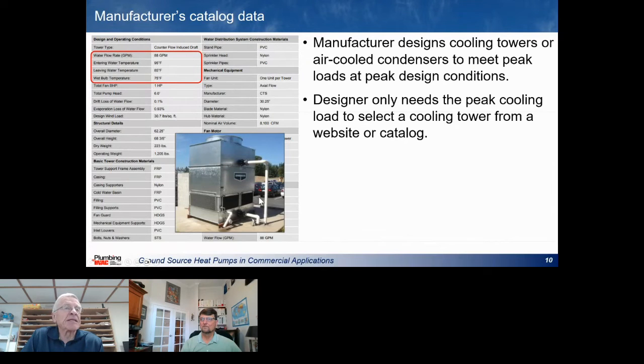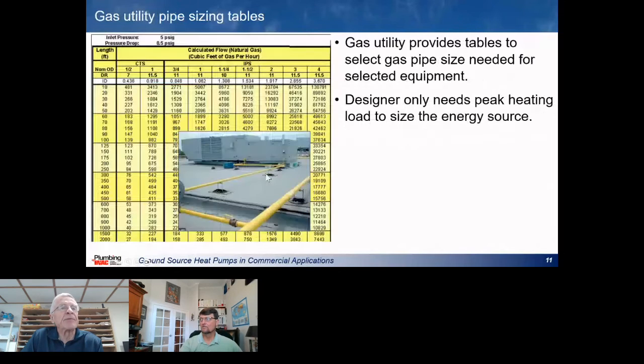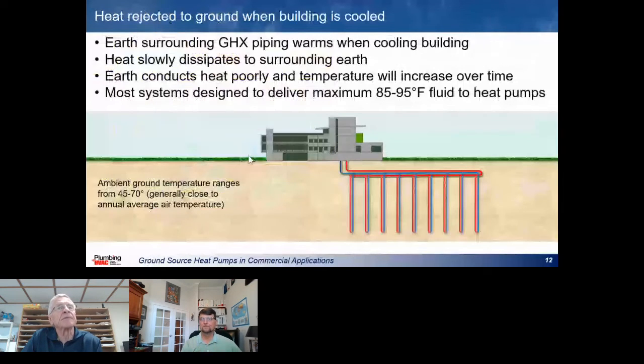These are designed basically, if you know what the weather data is that you're working with, you can select a cooling tower quite simply. You only need to know how many BTUs you have to get rid of. Same with the gas pipeline. If you're connecting to a gas pipeline, you've got an infinite source of energy. As long as you're paying the bill, all you need to know is how many BTUs you have to deliver to that equipment on the worst day of the year. And that's the extent that you have to worry about the energy source.